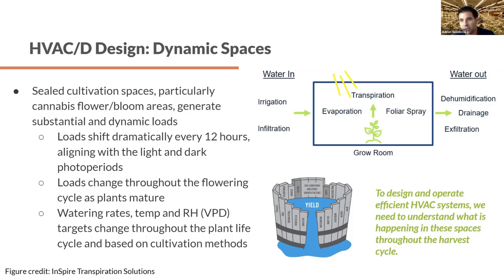The graphic there on the top highlights some of the moisture dynamics that we have to be really aware of when we're designing and sizing systems. There's a lot going on in these spaces, and like Brian just talked through, from our experience, everybody's experience in the space, the dehumidification systems and the moisture removal really need to be focused on first and understood, so that we remove the moisture in the appropriate ways at the appropriate times.